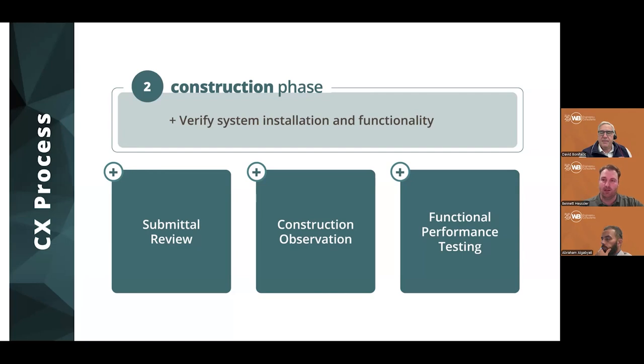Things like this we catch, and they lead directly to energy savings. There was an example where an air handler serving 100,000 square feet would save about $6,500 in annual savings just by setting up this one sequence. These are things that design engineers spend a lot of time thinking about, and if it's not installed correctly, where did that effort go?